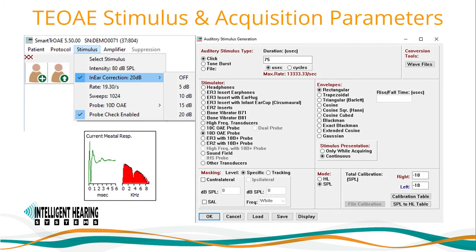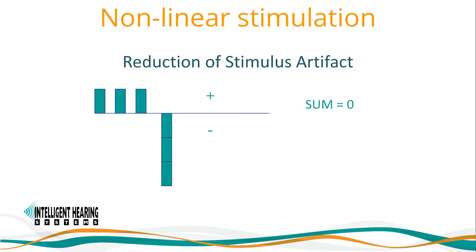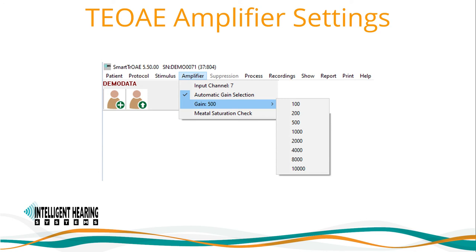In the stimulus menu, you can set up various acquisition parameters such as selecting your stimulus type, intensity, in-ear calibration range, rate, sweep count, probe selection, and probe check. TEOAE responses are mostly click evoked, at testing levels of 85 to 95 dB SPL, using a 75 microsecond duration biphasic alternating click with spectral energy from 500 Hz to 5000 Hz. The non-linear stimulation is used to reduce stimulus artifacts of high intensities. The amplifier gain can be set to be chosen automatically by the testing software or manually selected. All selections can be saved as part of your default settings in the protocol menu.